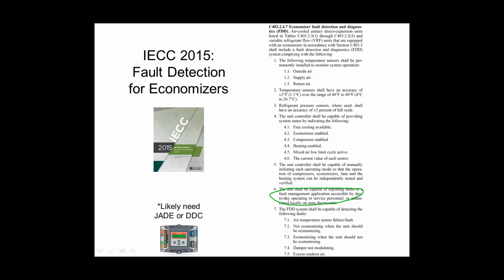So all this stuff in the code, the entire IECC code book, is not the responsibility of the equipment manufacturer to comply with. And I'm probably saying, oh, Ryan's saying that because he works for a rep firm, right? I'm saying that because every single state is different, and the manufacturer makes all kinds of equipment, many of which you can't even use in the state of Illinois. If you were on the January webinar, every single package rooftop on the entry level from every single manufacturer, you can't use in Illinois anymore. You have to go up to the mid-tier or high tier to comply with the code just for rooftop efficiency. So the manufacturer is going to make all kinds of different stuff for all different states and cities and municipalities that have different codes. So they're still going to make stuff that doesn't comply with Illinois.